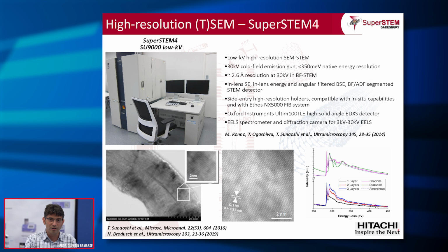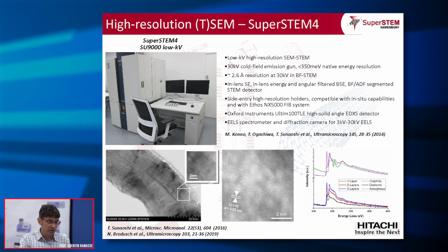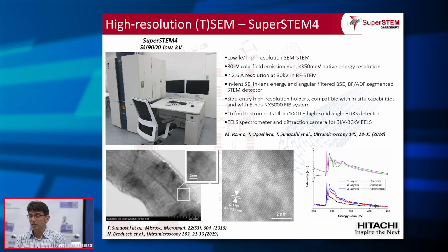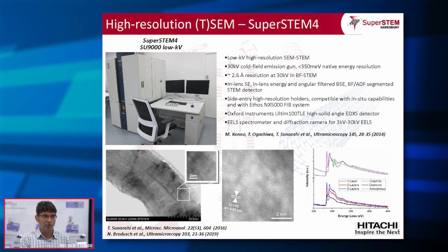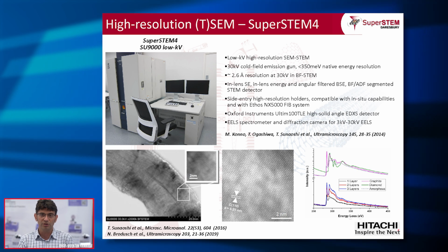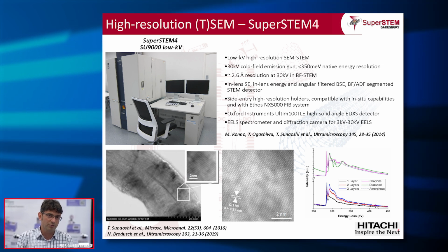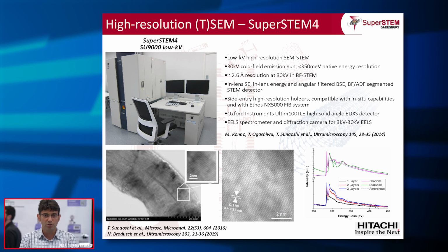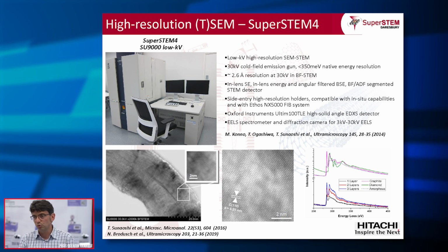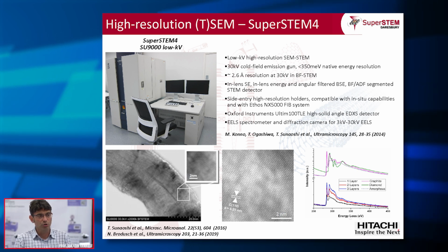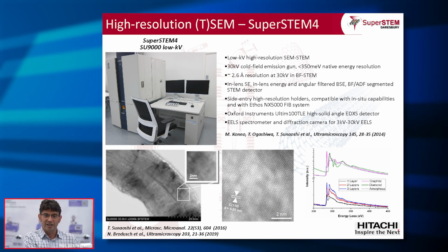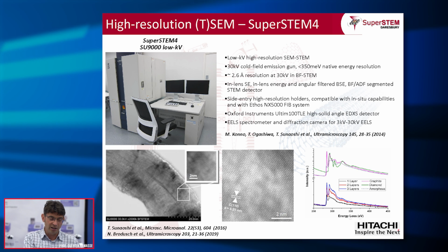But then the clincher came when people told us that all the way back in 2016, you could use an EELS system and adapt it to this instrument. That really caught our attention. If you have a cold field emission source, that's 350 millielectron volt energy resolution and 2 to 3 angstrom spatial resolution, provided your sample is good enough. But remember, our focus was to make samples thin enough and good enough to get there.